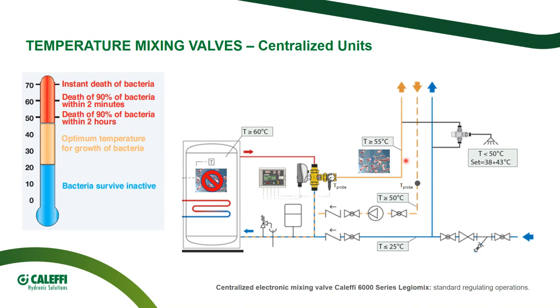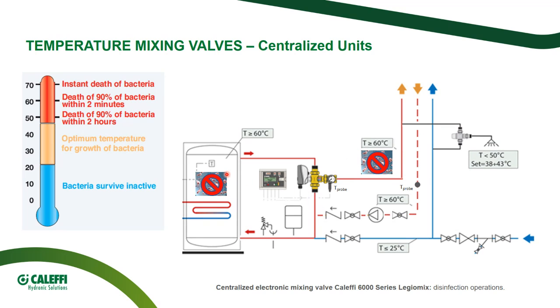So if you imagine how big can be the recirculating loop of a tower or a hospital or a medium mix, we have liters and liters and kilometers of pipe exposed to Legionella growth and proliferation. So the digital mixing valve Caleffi Legiomix is able at a certain time, at a certain temperature, usually in the night, to perform the thermal disinfection of the system. It means that the cold water inlet will be completely shut off, and the water at the same temperature of the storage will flush the whole system for a certain period of time that we will fix.